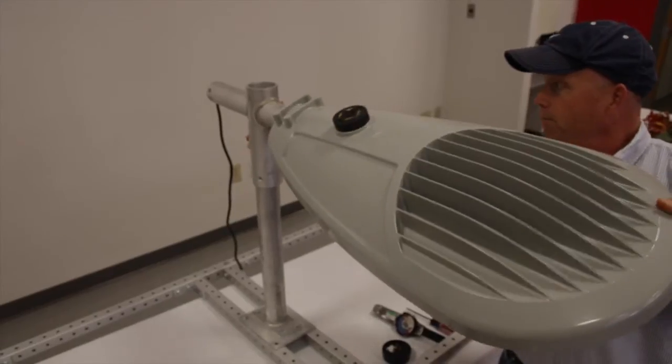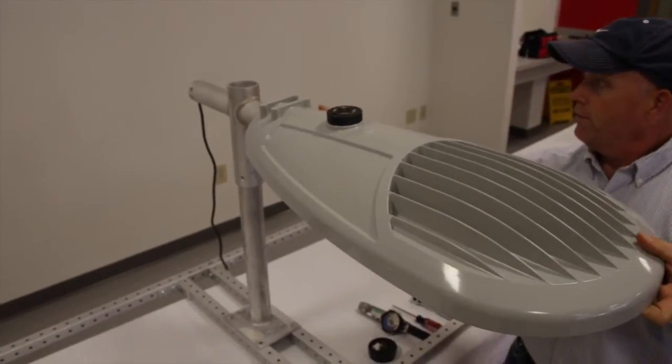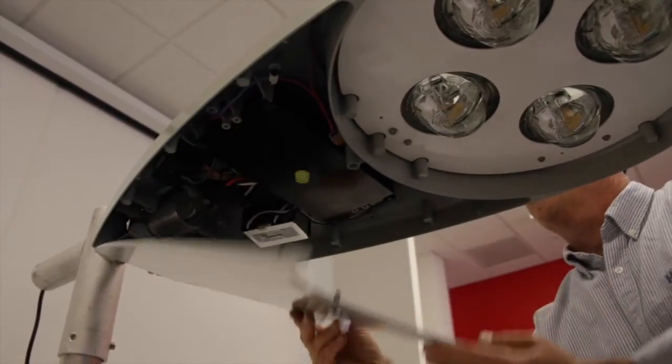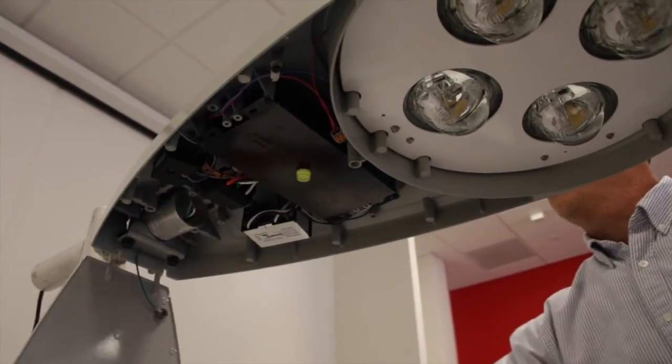If you are mounting your ATBL onto a larger diameter arm, remove the two knockout plates with pliers. Now slide the fixture onto the arm until it stops. Next, loosen the wing screw and open the door to check the bubble level and ensure that the luminaire is level.